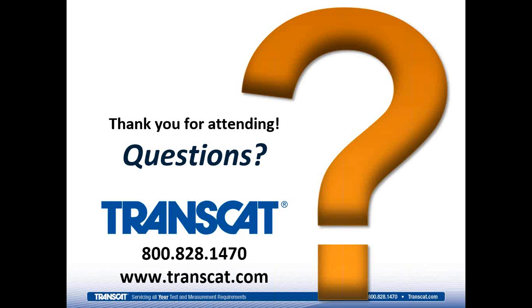Yeah, so again, distinctly separating PAR from PUR. PAR just uses the tolerance of the instrument in the denominator, and the PUR would include other factors that you put into an uncertainty budget, which I won't go into detail here, but that includes at a minimum the accuracy of the instrument, as we did with PAR, but also the uncertainty of the calibration of that instrument, the resolution or repeatability of that instrument, and any other factors that would be considered major factors in making a measurement. So PUR would consider all of those things combined together to give that denominator value.